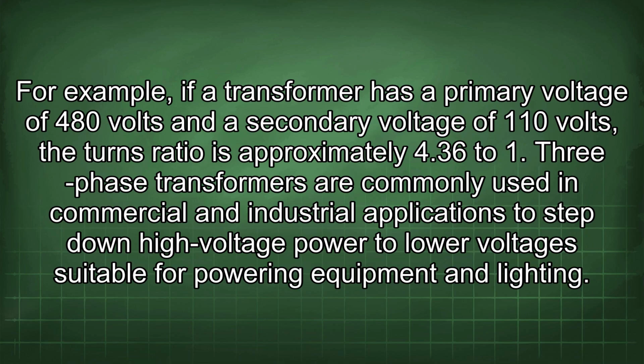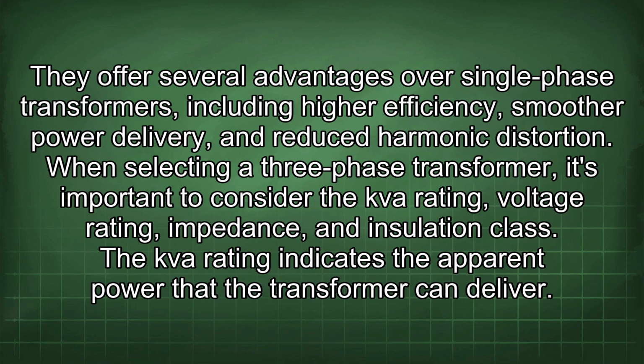The ratio of the primary voltage to the secondary voltage is determined by the turns ratio of the transformer. For example, if a transformer has a primary voltage of 480 volts and a secondary voltage of 110 volts, the turns ratio is approximately 4.36 to 1. Three-phase transformers are commonly used in commercial and industrial applications to step down high voltage power to low voltages suitable for powering equipment and lighting. They offer several advantages over single-phase transformers, including higher efficiency, smoother power delivery and reduced harmonic distortion.